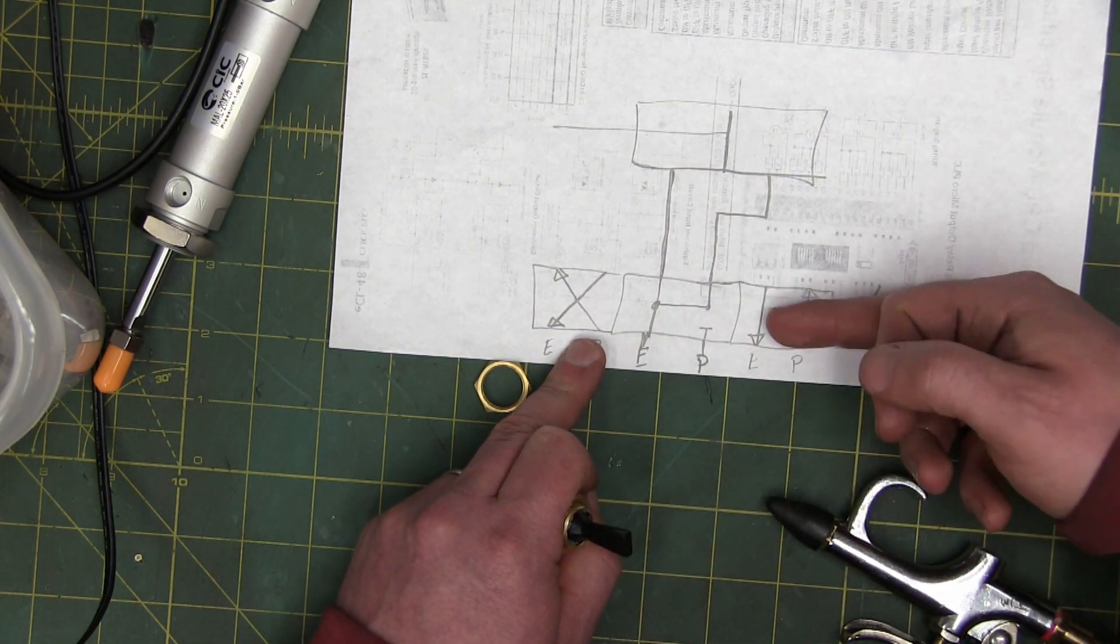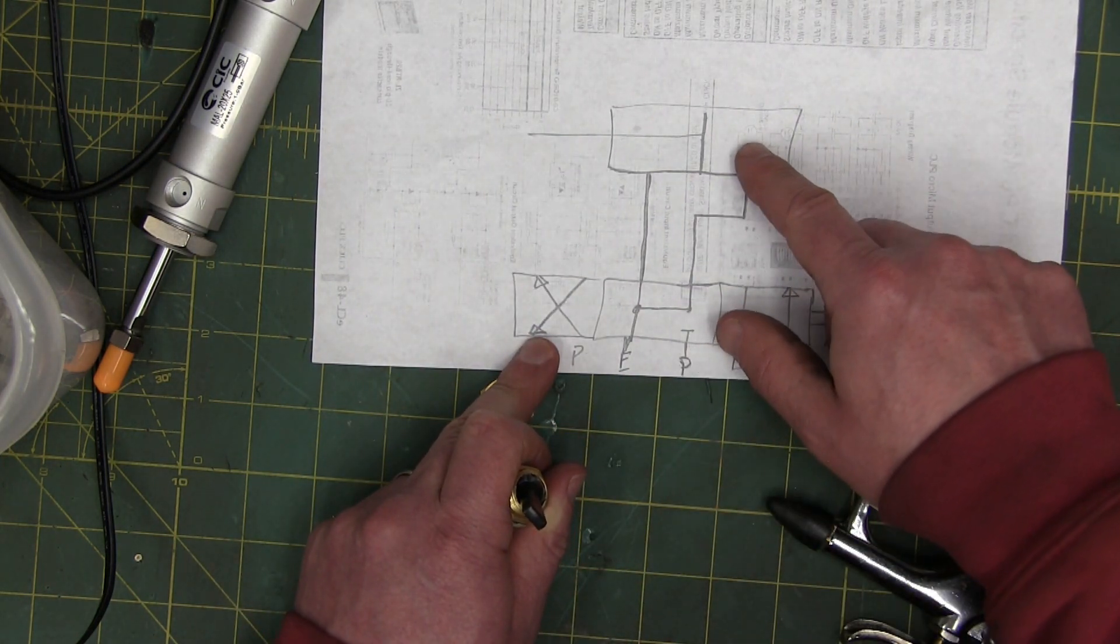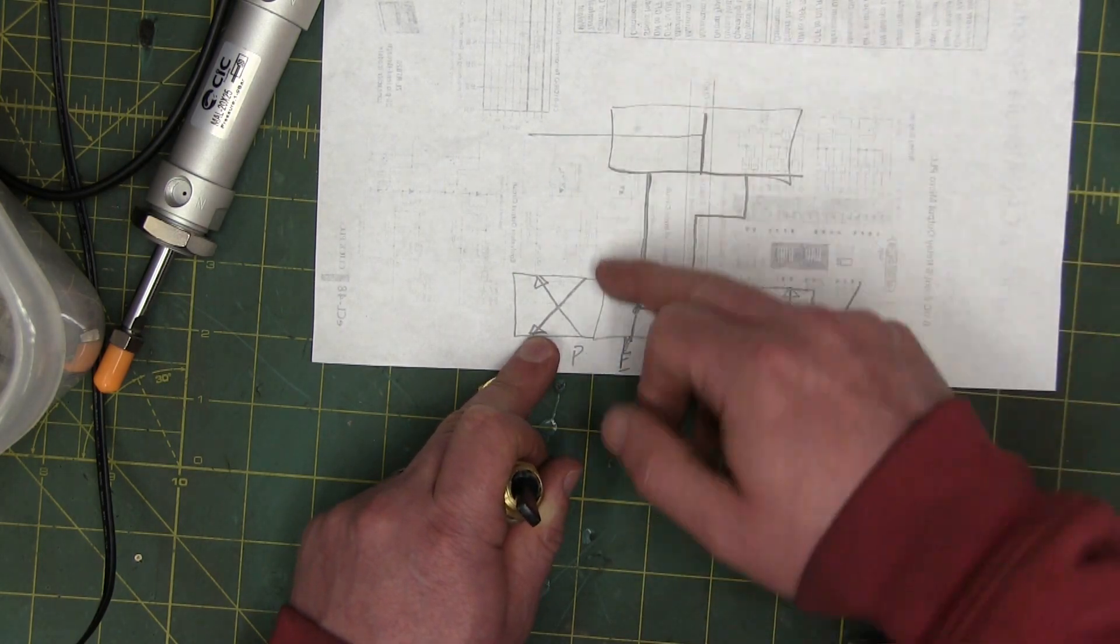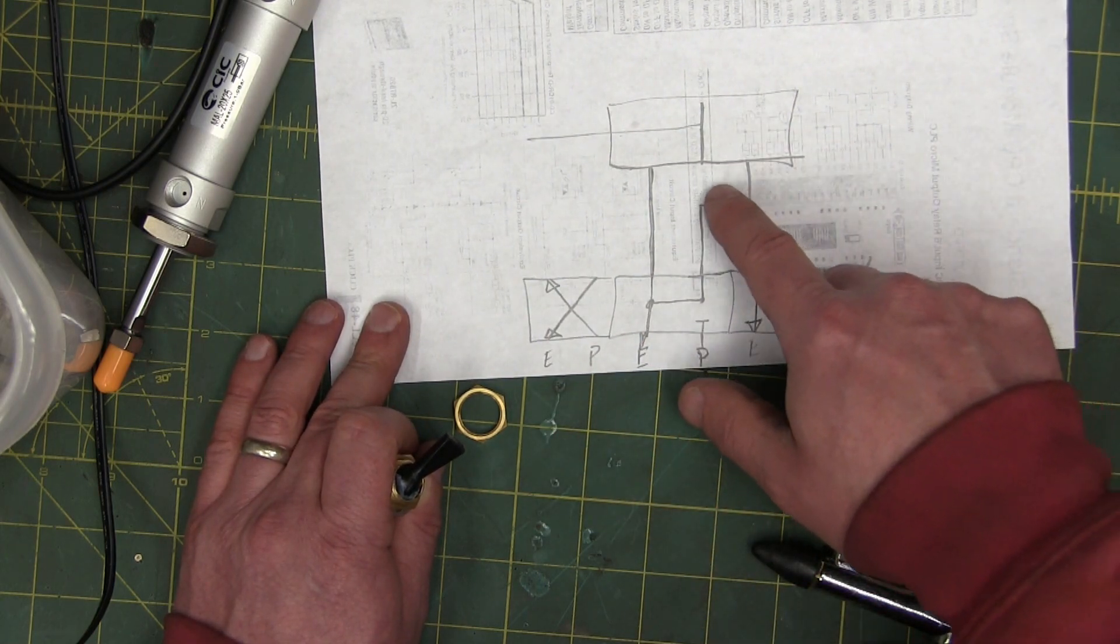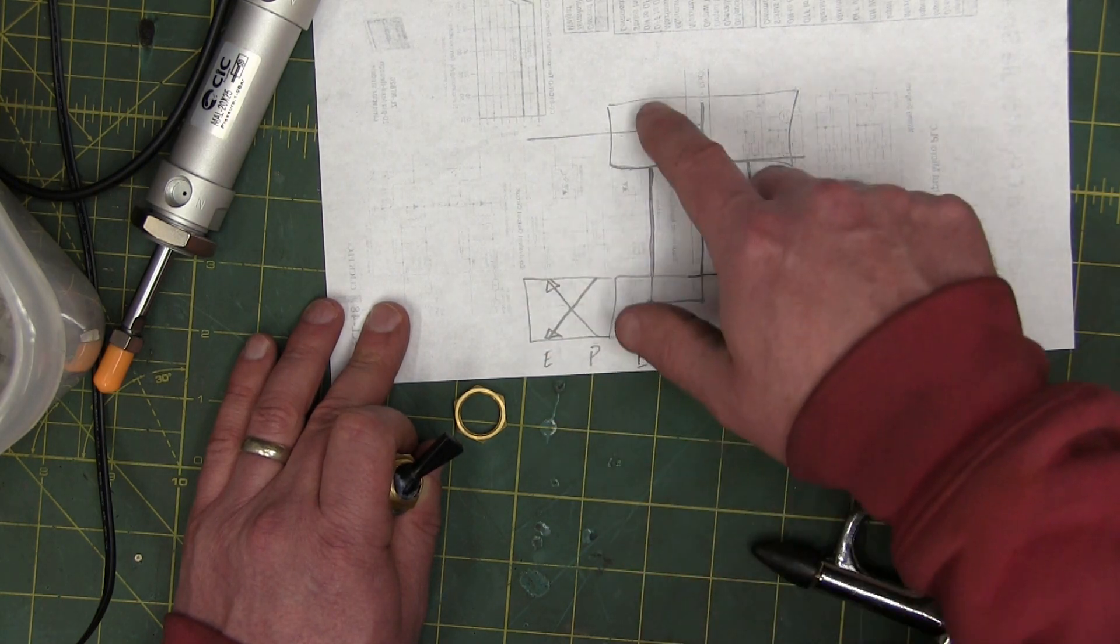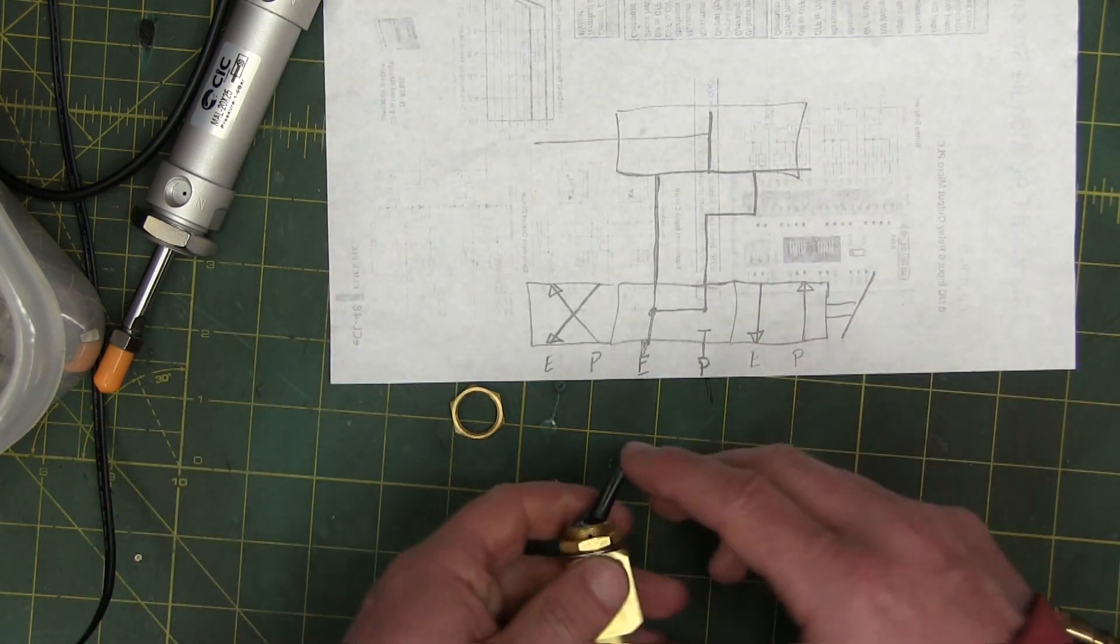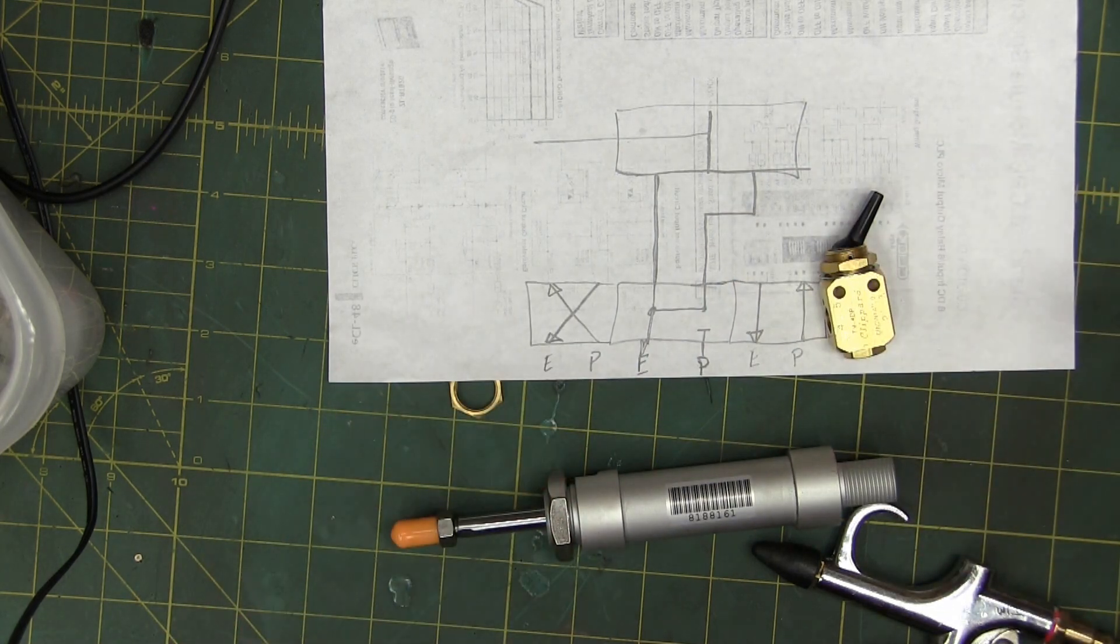Then if we toggle the valve over, we get pressure in the one side and the other side exhausts that allows us to extend the cylinder. And if we pull the toggle all the way over the other way, we swap those lines and this pressure exhausts and this pressure goes into the gland end and retracts the rod. That's how the thing works. So we're going to hook it up and I'll show you how that's going to work.